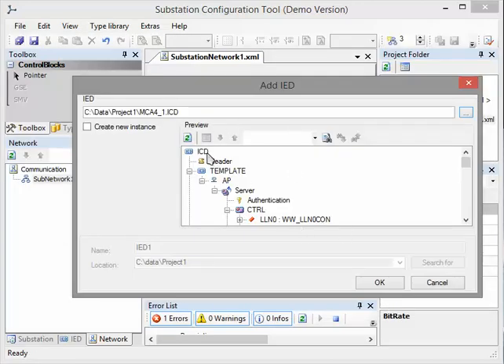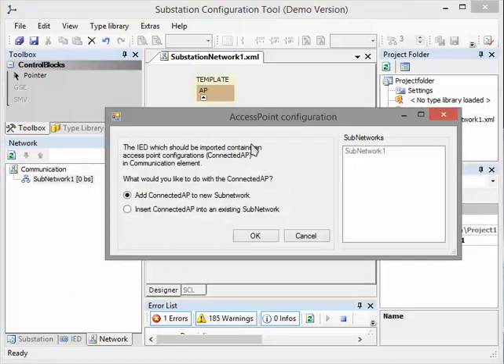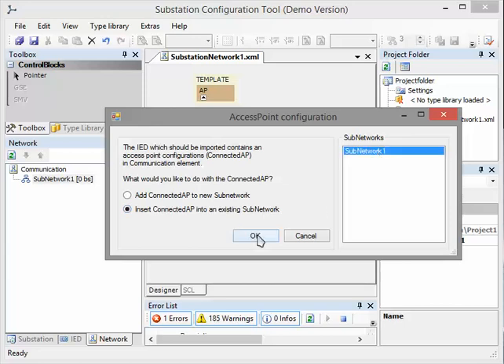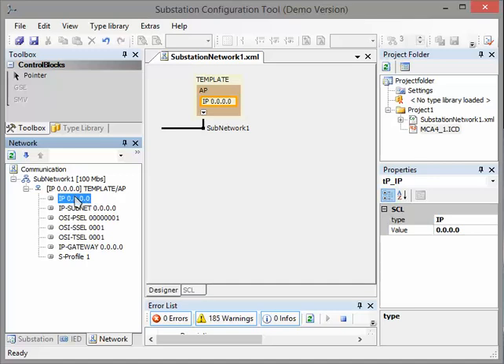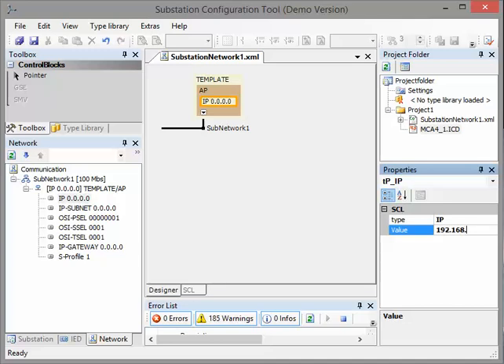Now you see all information was ready to import. I say OK. Now the tool asks us whether we want to add this protection relay to our substation network. We say 'Insert into an existing substation network' and we choose our network. Click OK. Now the device is loaded into our substation network, but the IP address is not correct, so we have to change it. We click here on IP address — for example, 192.168.1.1. This is the IP address of our protection device inside of our substation.